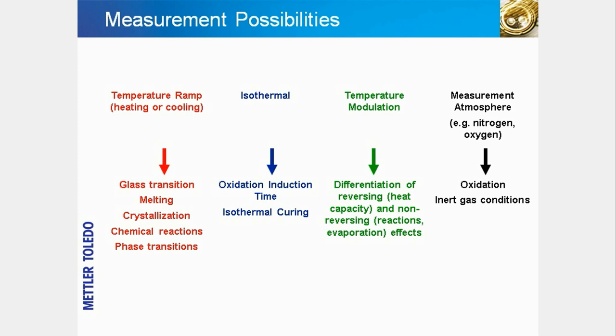DSC measurements can be performed dynamically using a linear temperature ramp, isothermally, or with temperature modulation. Temperature scans are used to investigate temperature-dependent processes such as the glass transition, crystallization, melting, and curing reactions. Isothermal temperature experiments are mainly used to determine the oxidation induction time of materials or to study chemical reactions. Temperature-modulated experiments enable you to separate reversing and non-reversing effects, for example the glass transition from simultaneously occurring reactions or evaporation. Special atmospheres, such as pure oxygen or nitrogen, are often used to accelerate or prevent the decomposition of samples.